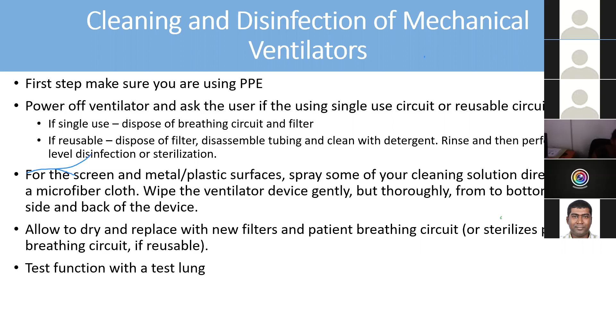For the screen and metal or plastic surfaces, spray some cleaning solution directly onto a microfiber cloth and wipe the ventilator device gently but thoroughly, including the bottom and the side and back of the device. Clean it properly. Okay, allow it to dry and replace with a new filter and patient breathing circuit, or sterilize the patient breathing circuit if reusable. Then power up and test run the unit with the test function using a test lung. So you see whether it functions properly, to make sure the device is ready to use.